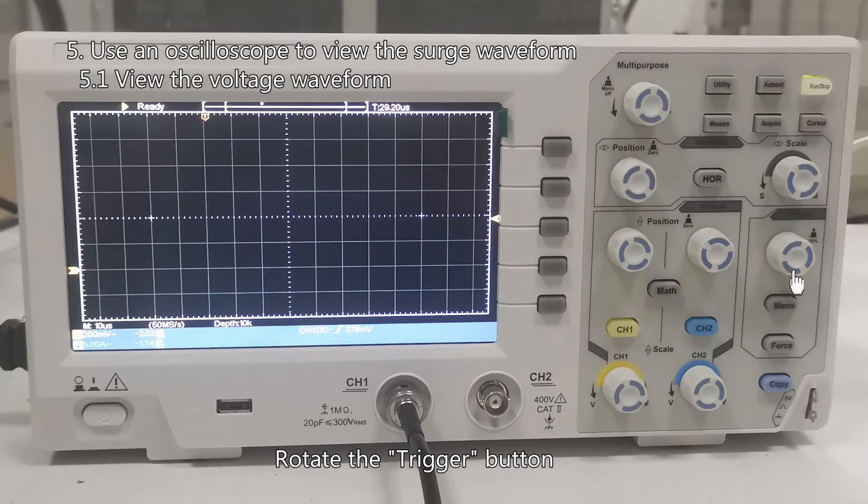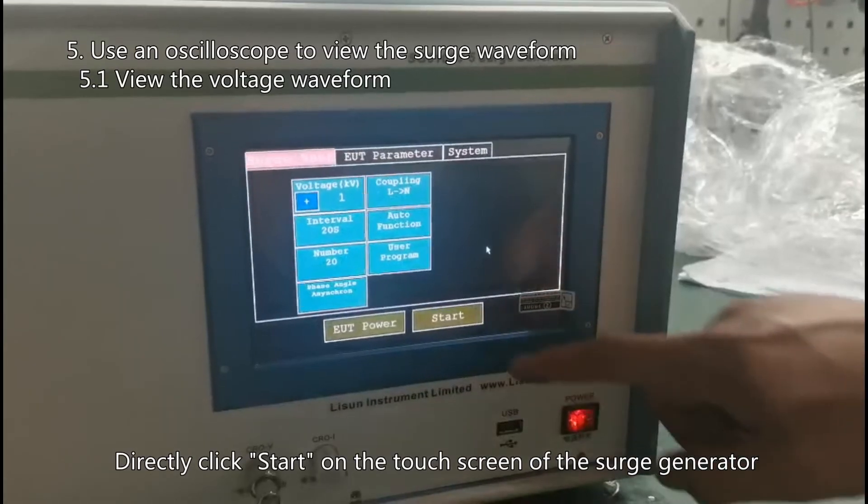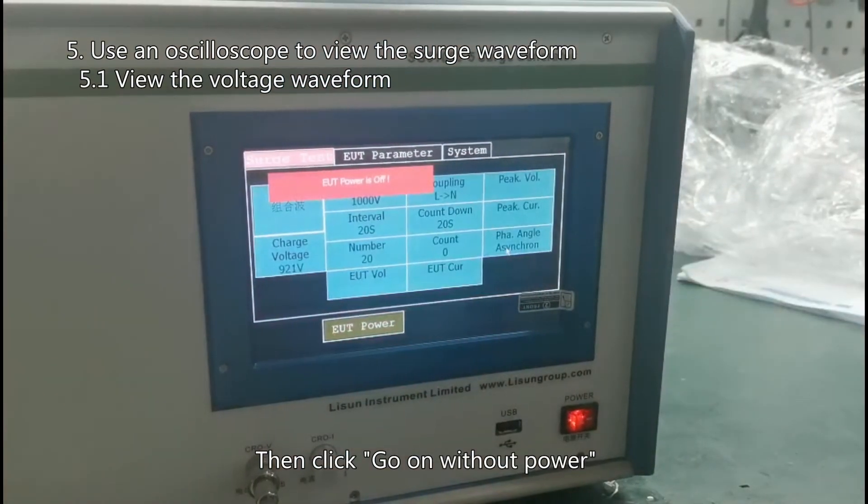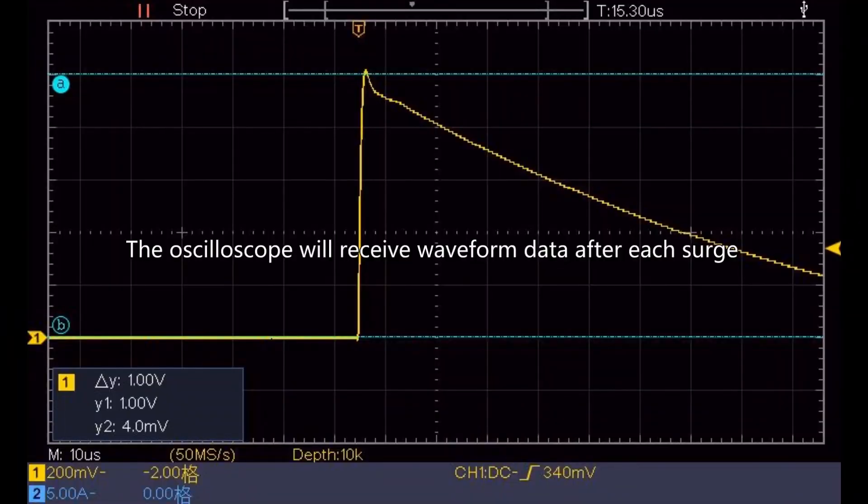Rotate the trigger button. Adjust the trigger level to the approximately middle position. Directly click start on the touch screen of the surge generator. Then click go on without power. The oscilloscope will receive waveform data after each surge.